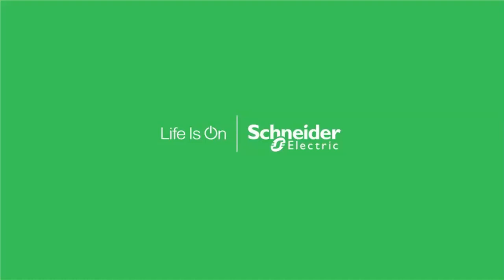Great. The next question is, if someone is interested in putting together an arc flash mitigation work practice strategy, where would they begin, and what would they need to do in terms of budgeting for that kind of strategy? Okay. I think one of the places to begin is, well, there's a couple of preludes to getting out there and mitigating arc flash levels themselves. One of them we mentioned toward the end of the presentation. One of the first places to start is doing an analysis. How do you know what to fix until you've quantified what the arc flash levels are in the facility? There are different ways to do arc flash evaluations, but whatever they are, do those, and get a handle on the levels that you have in your facility.